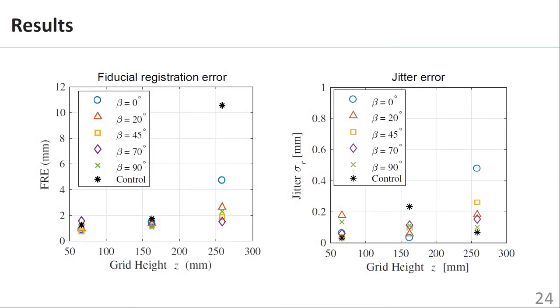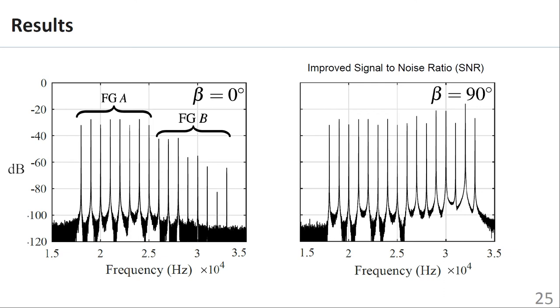The following plots show the total fiducial registration error and jitter error for various tilt angles beta. Control measurements were performed using a single field generator A. In general, it can be seen that increasing the tilt angle reduces the total system jitter and fiducial registration error. This improvement correlates with an improvement in overall system signal-to-noise ratio.